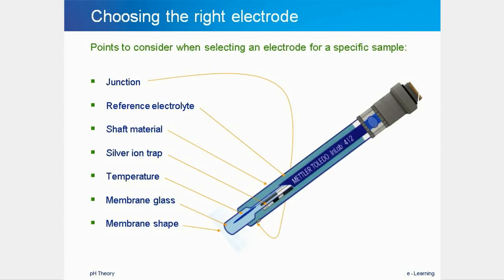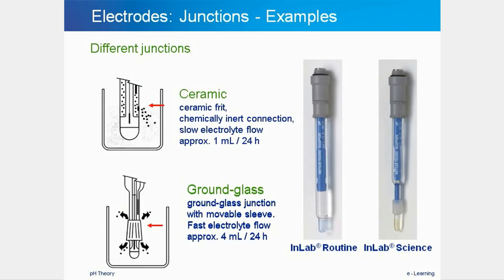Mettler Toledo manufactures many different pH, reference and combined pH electrodes. Different samples need different electrode properties for the quickest and best results. The important factors are the shape of the membrane glass, whether a temperature sensor is present, which reference system is in the electrode, and the material of the outer shaft which will be in contact with the sample. Also of interest are the reference electrolyte solution and the junction or diaphragm through which the reference electrolyte flows out into the solution.